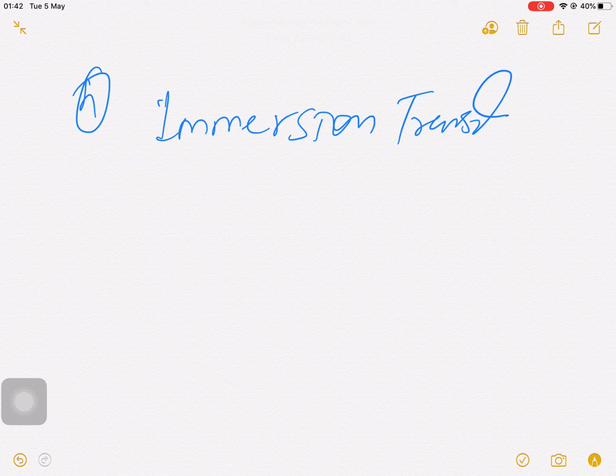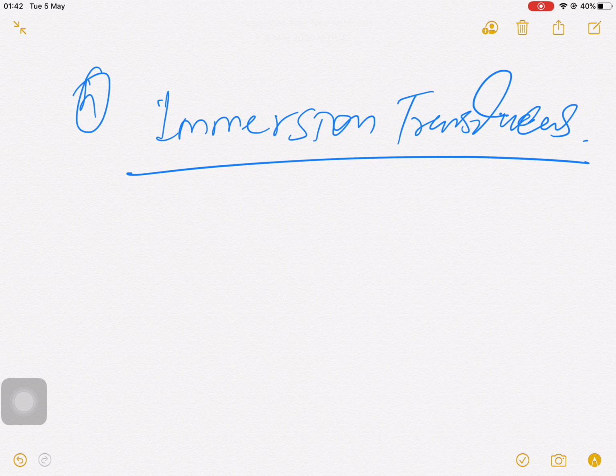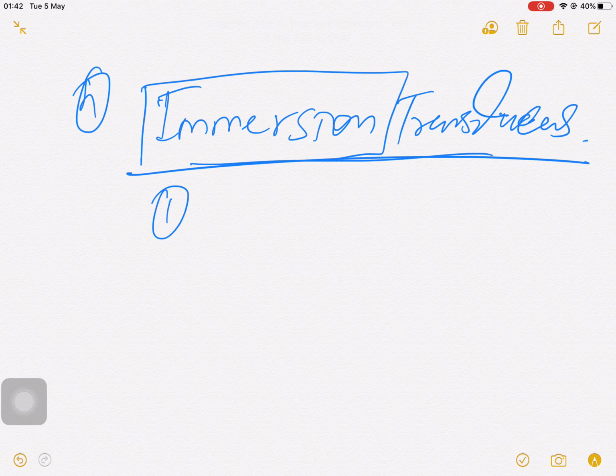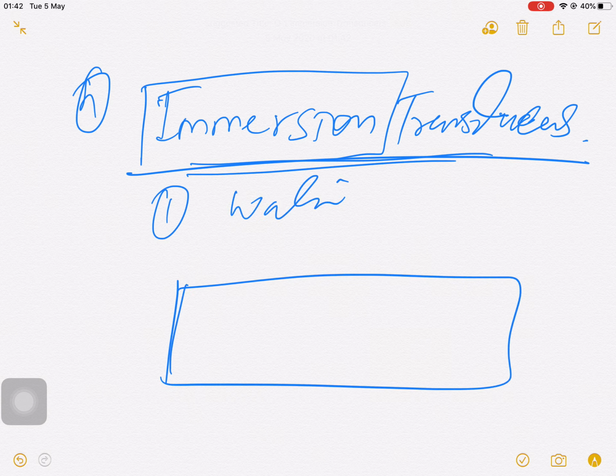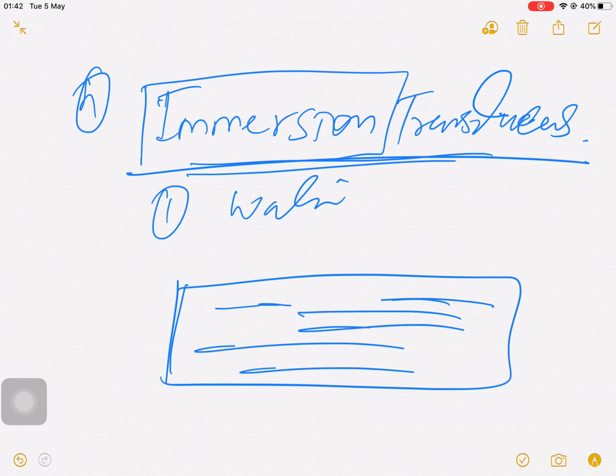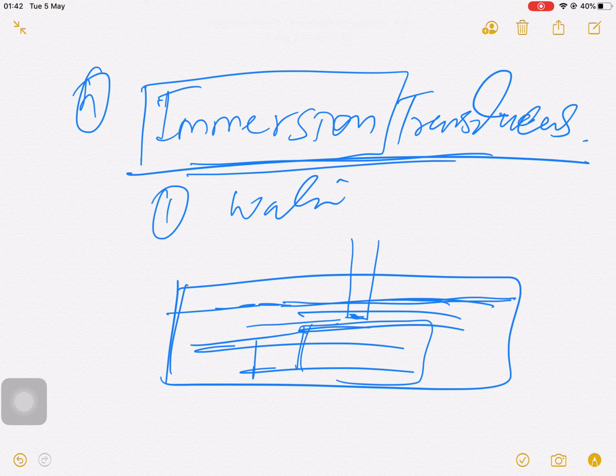Okay, so immersion transducers, as the name implies, are designed to be immersed in water. So as you understand, an immersion transducer will generally be immersed in water. It will be like this: a tank full of water, and here will be your test piece. So the transducer will go like this, inside the water. This is the test piece, and this is the water level from the top.